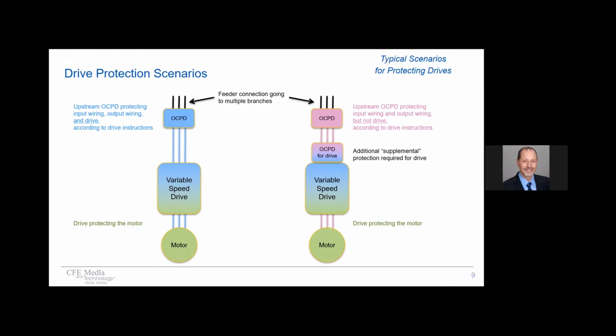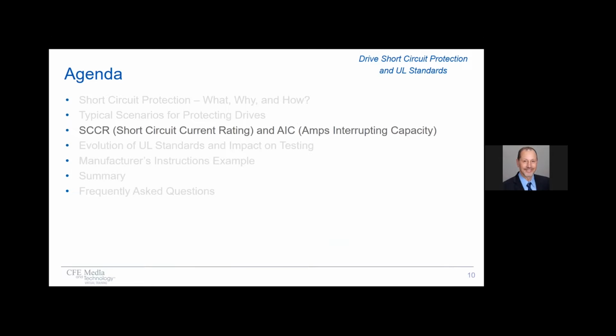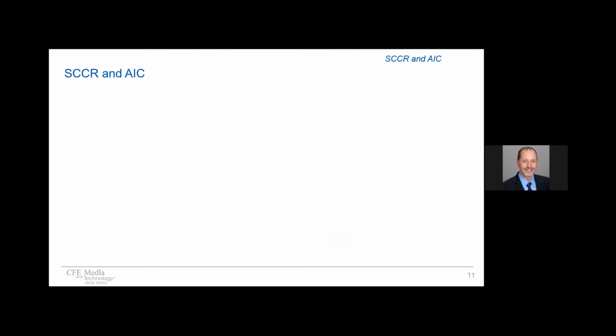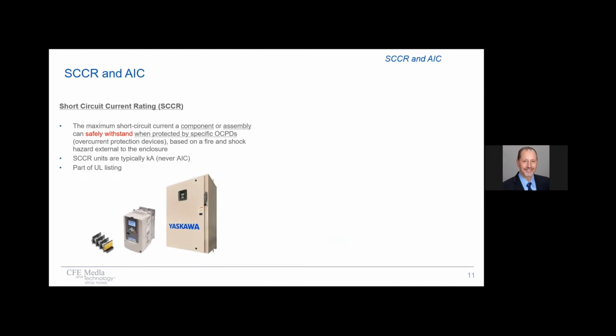Before getting more specific and diving into how UL is related to this, I want to take a few minutes to make sure we're all on the same page with some terminology. The terms short circuit current rating, or SCCR, and amps interrupting capacity, these two terms are related, but definitely different. Short circuit current rating is really the ability to withstand. And it's for components or assemblies, their ability to withstand when protected by protective devices based on a fire and shock hazard external to the enclosure. And the rating for these devices, for short circuit current rating, is typically kiloamps and never amps interrupting capacity for withstand.